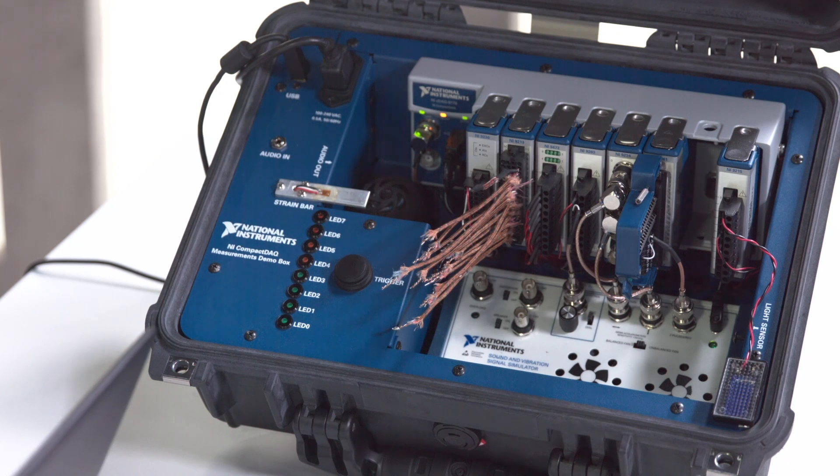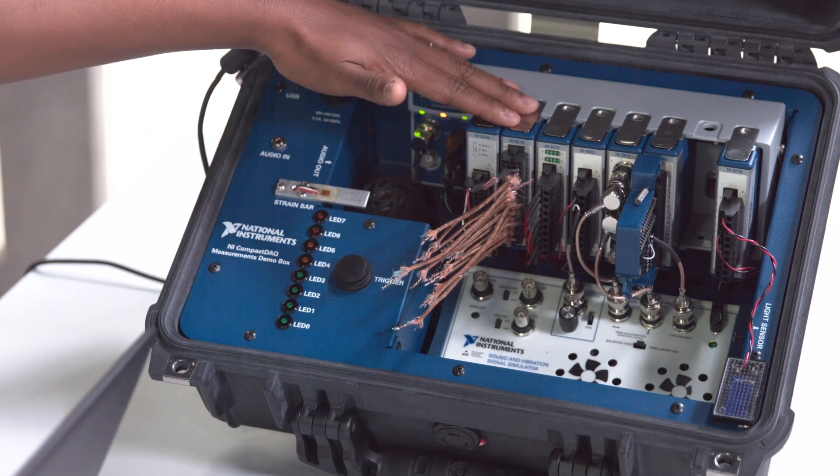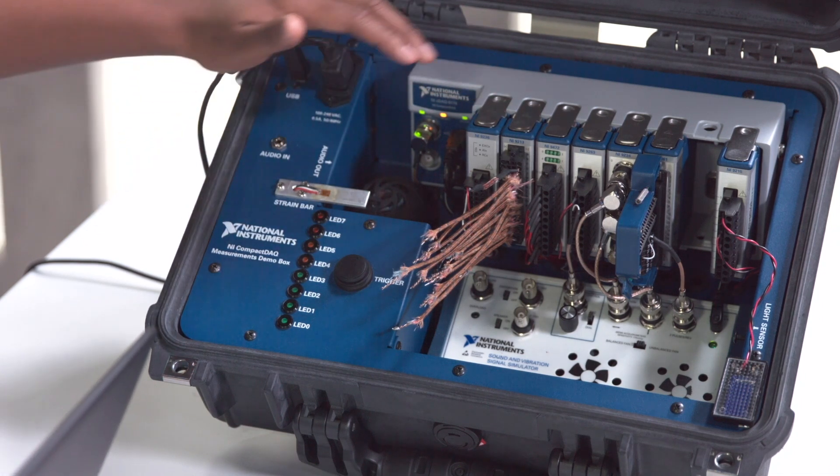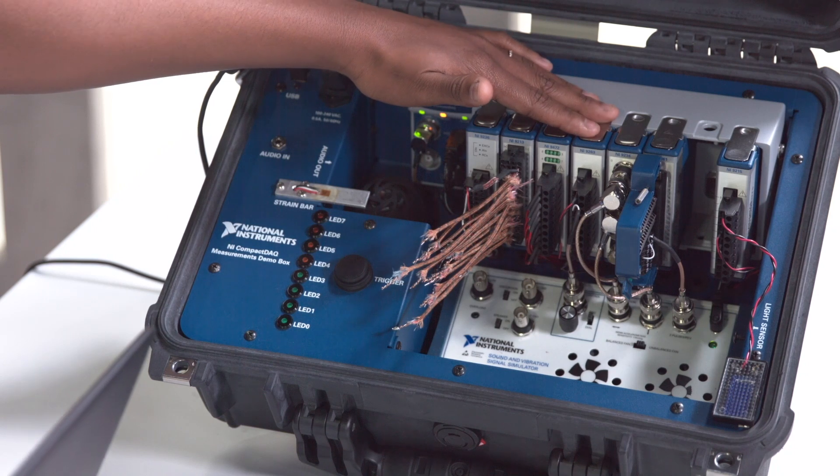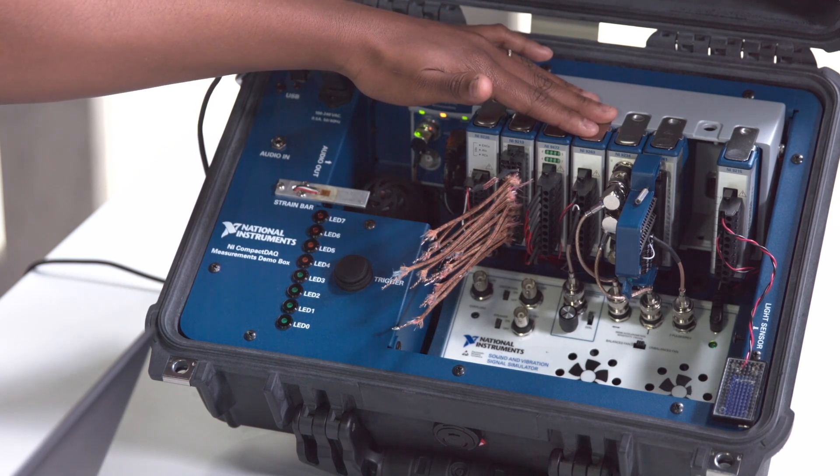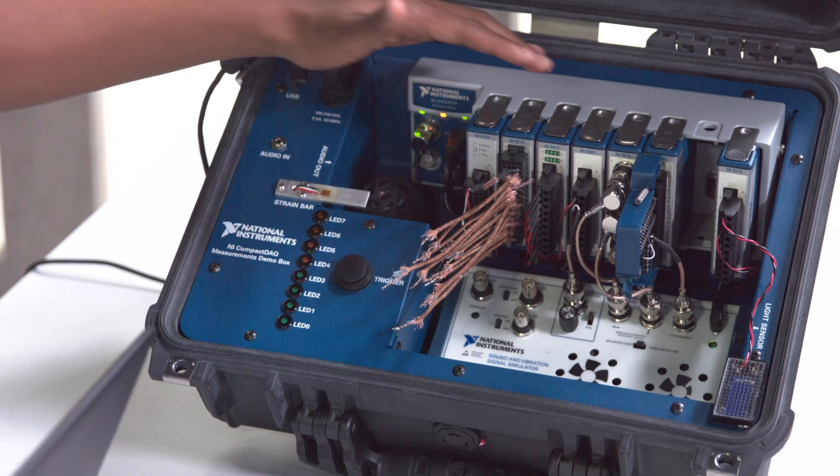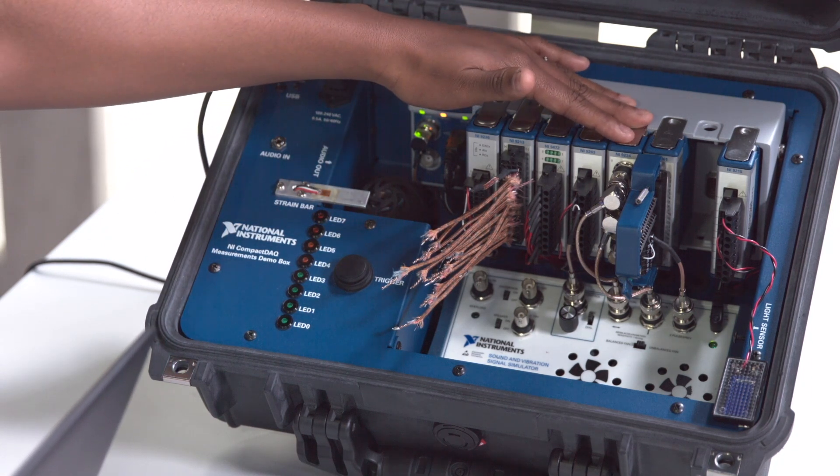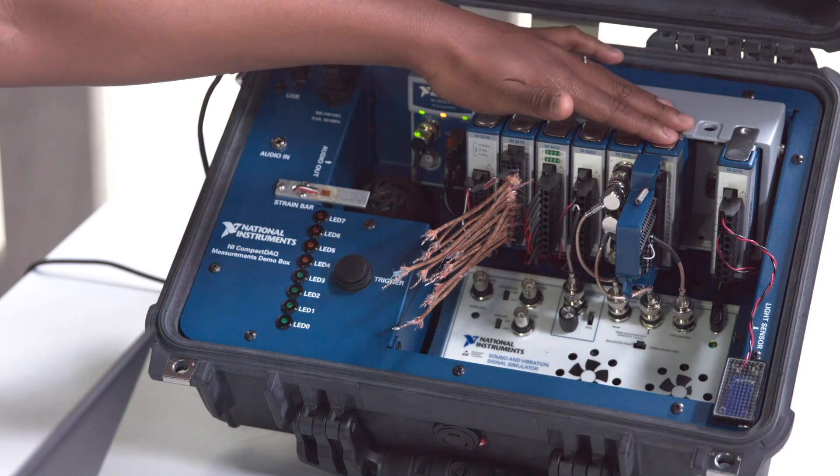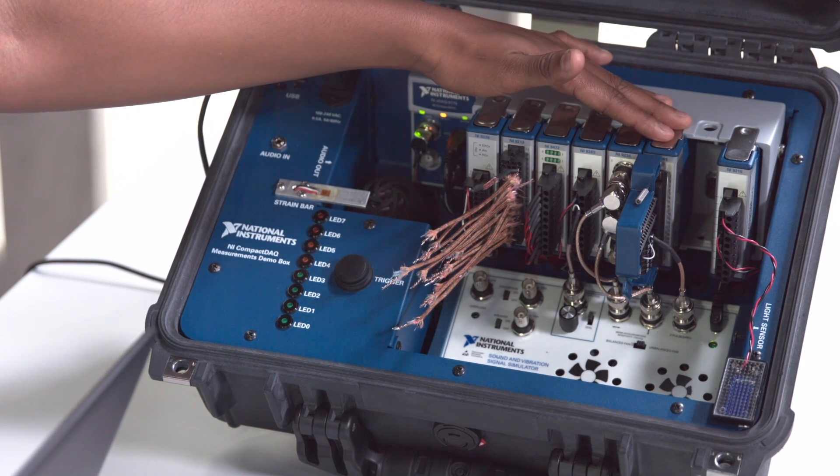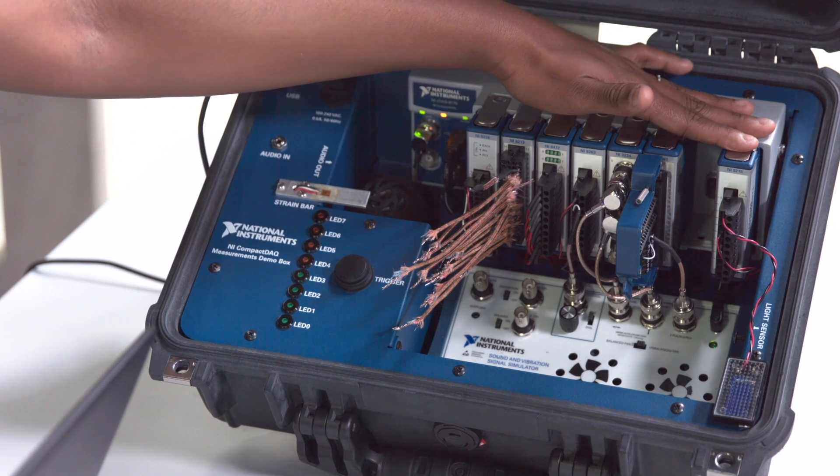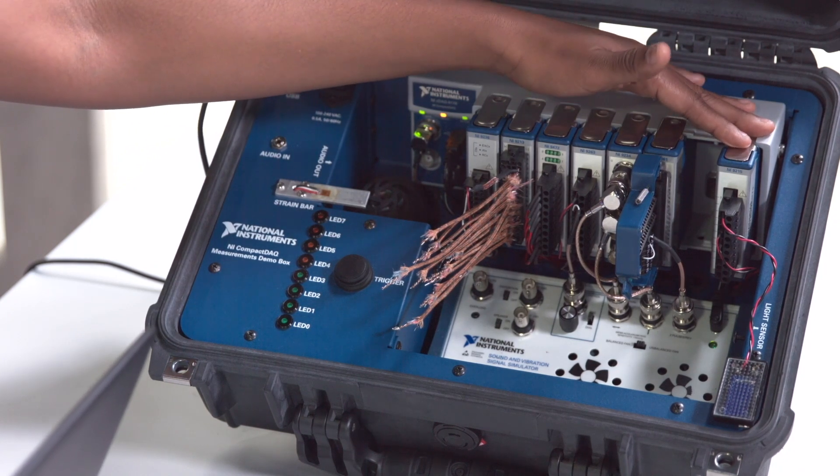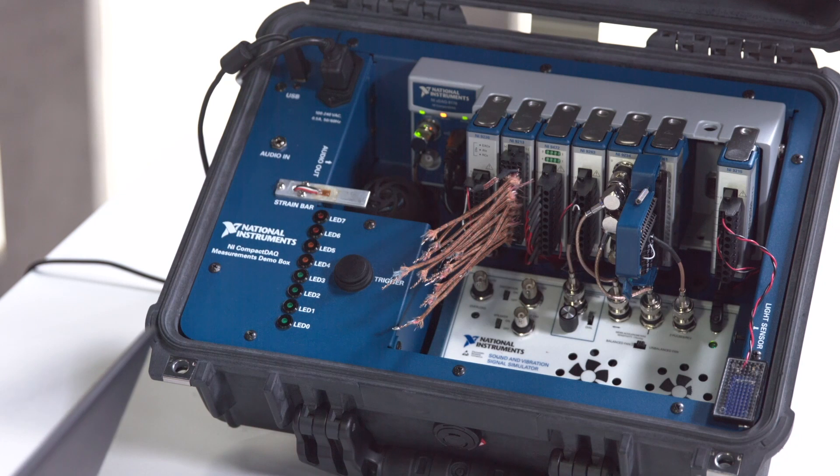So for our system today, we're going to be using a 9213 thermocouple module to measure the temperature of our simulated chamber, a 9263 analog output module to control when our fan turns on and off, a 9234 vibration module to measure the vibration of the fan, a 9361 counter module to measure the RPM or fan speed, as well as a 9215 voltage input module to measure the light sensor of our simulated chamber.